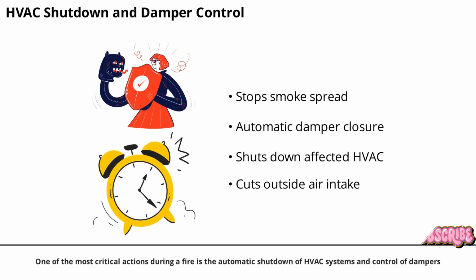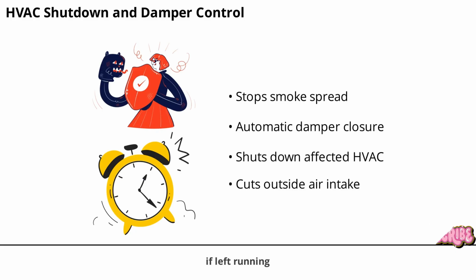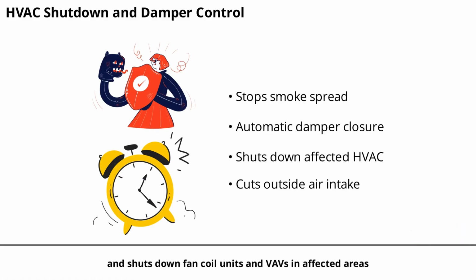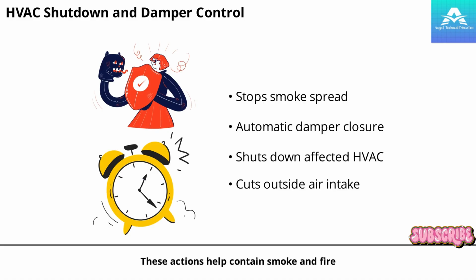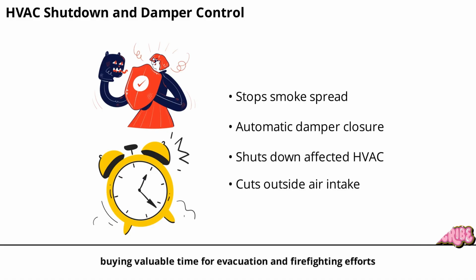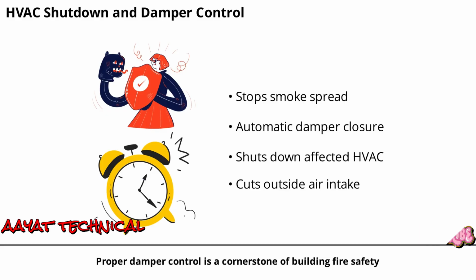One of the most critical actions during a fire is the automatic shutdown of HVAC systems and control of dampers. HVAC units, if left running, can spread smoke and fire between building zones. The BMS automatically stops supply and return fans, closes motorized fire and smoke dampers, and shuts down fan coil units and VAVs in affected areas. If an external fire is detected, outside air intakes are also cut off. These actions help contain smoke and fire, buying valuable time for evacuation and firefighting efforts. Proper damper control is a cornerstone of building fire safety.